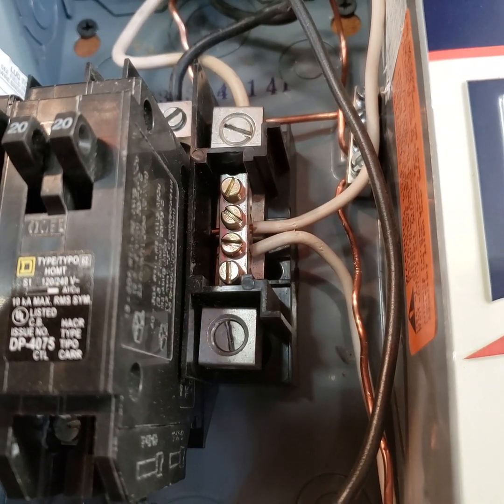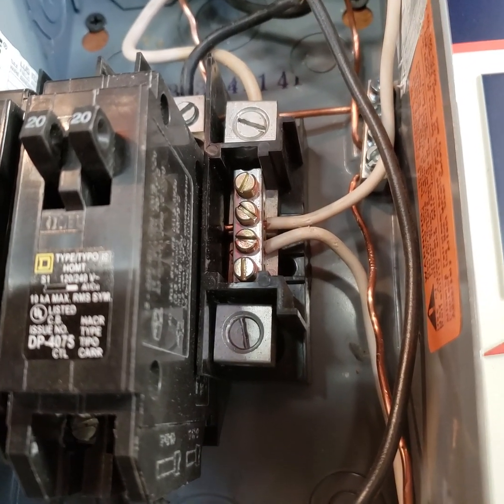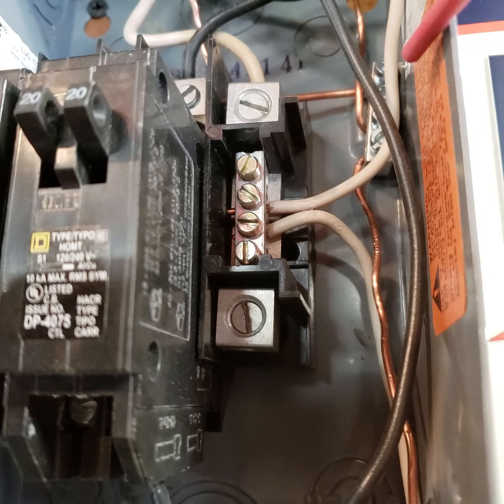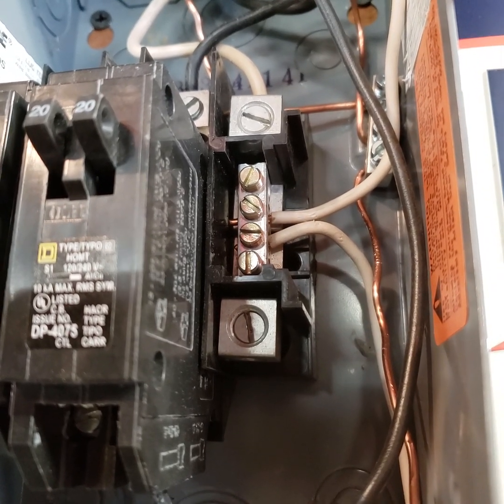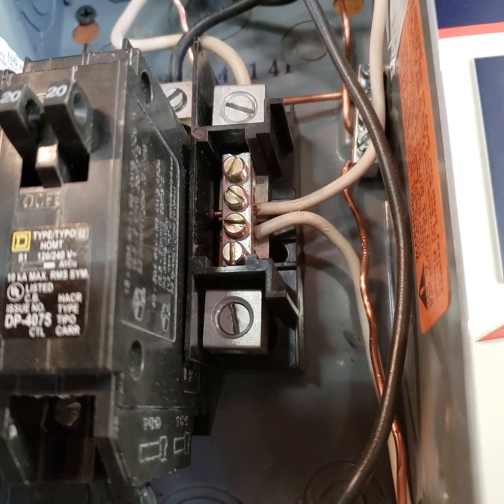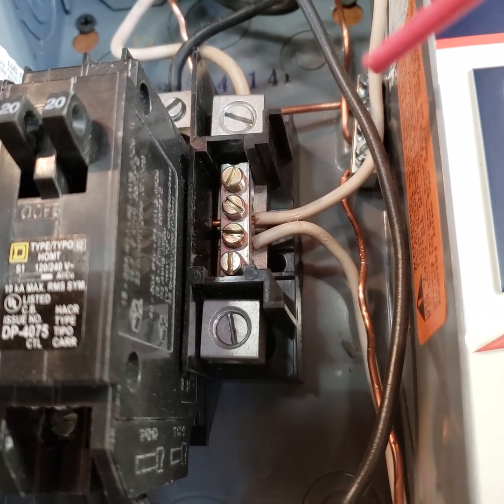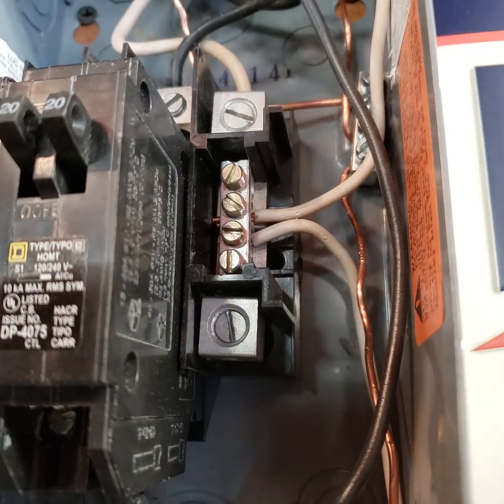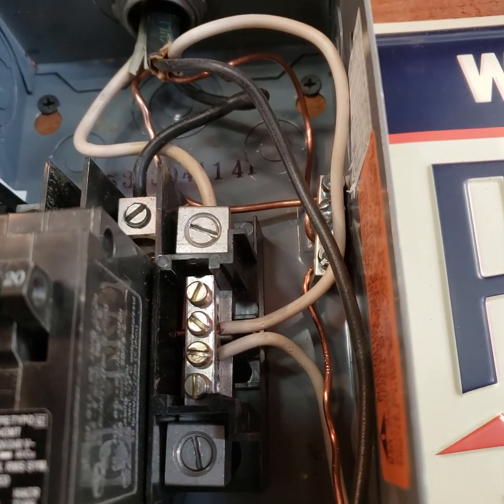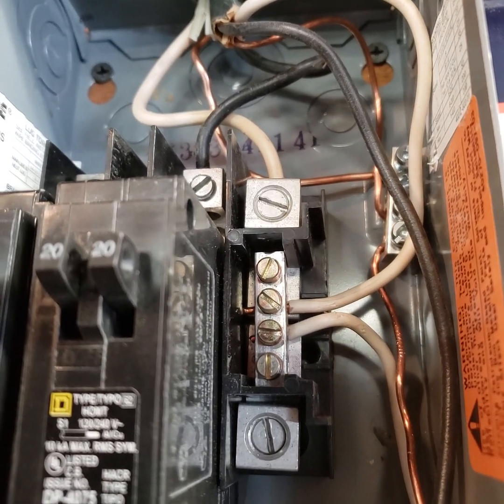—the current, say 10 amps, could split: five amps on the neutral and five amps on the ground wire. Then say something happens to the ground wire — you can have arcing issues, a faulty ground, or someone assumes it's dead and touches it while grounded somewhere else. They're going to get a shock from that five amps the ground wire is carrying. That's why you don't do that. There's a good demonstration video online on this, but I figured I'd make my own take and show what a sub-panel looks like.